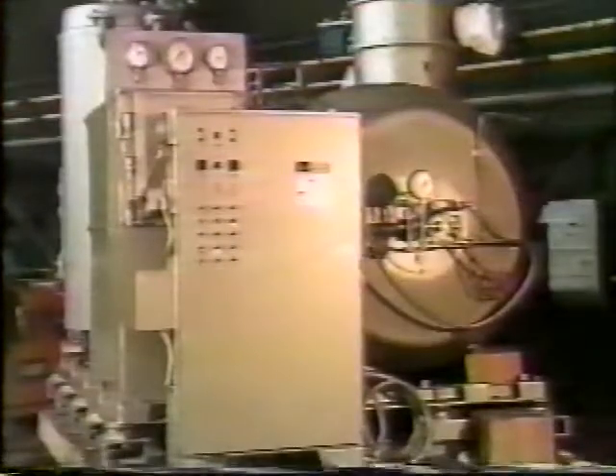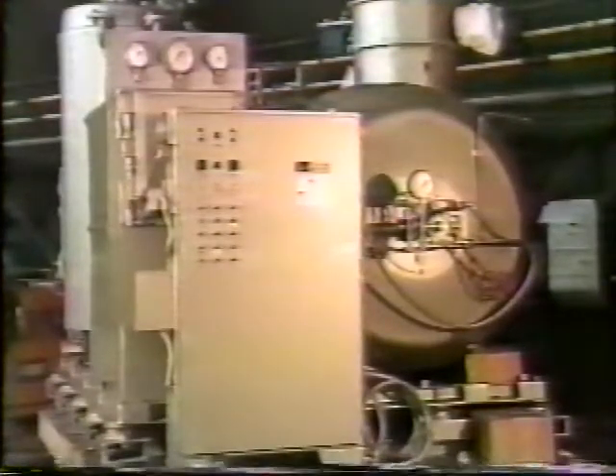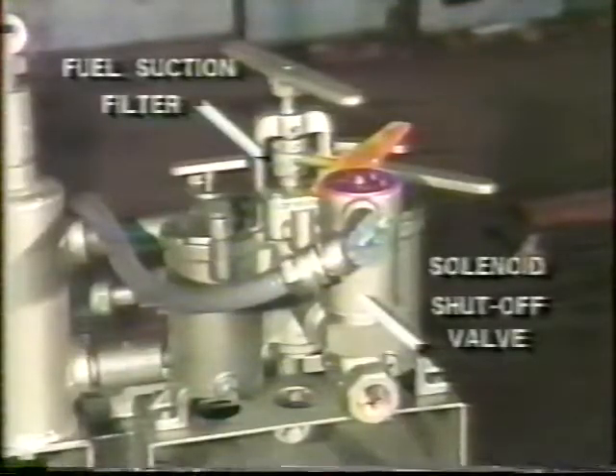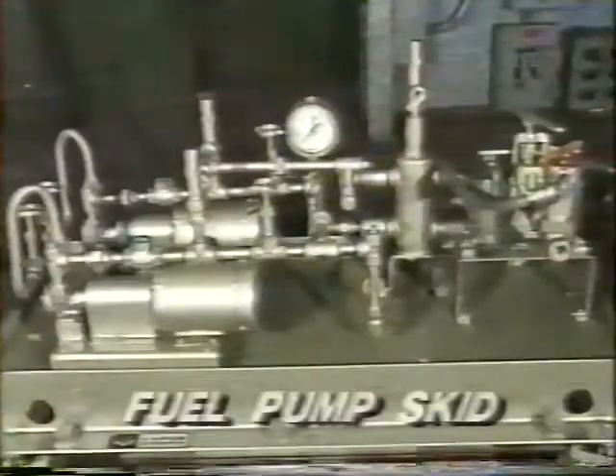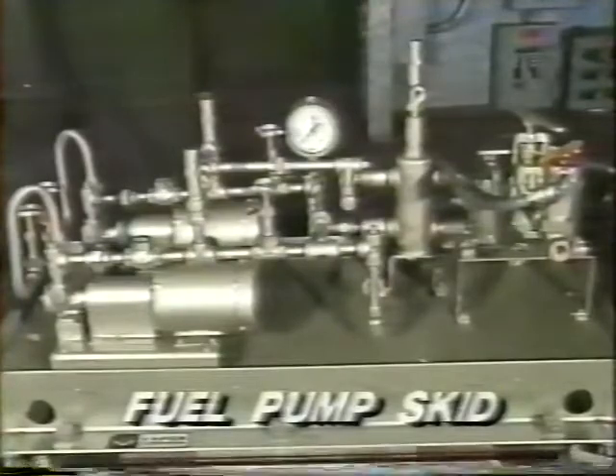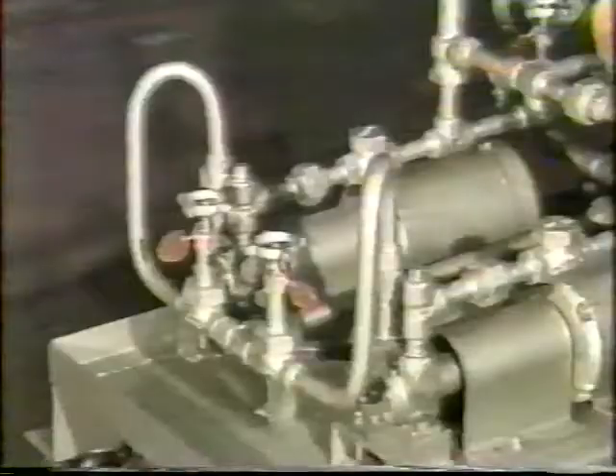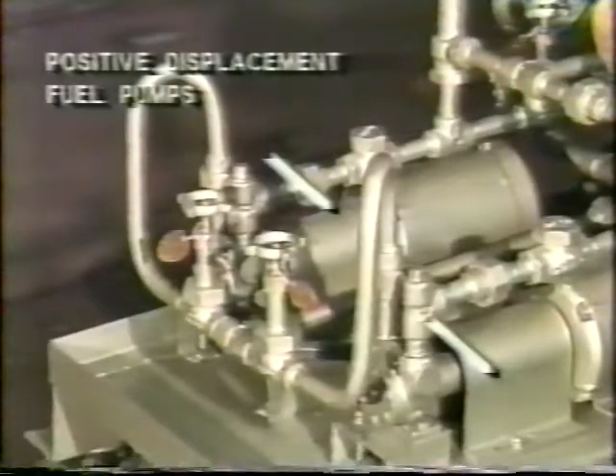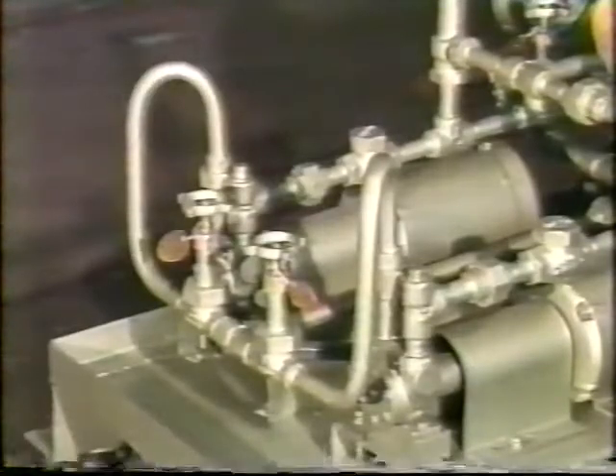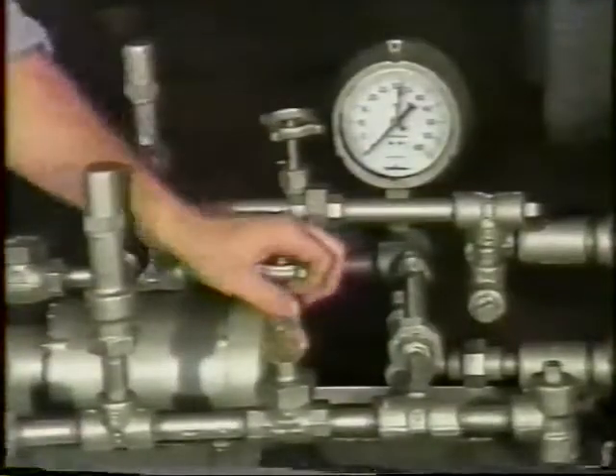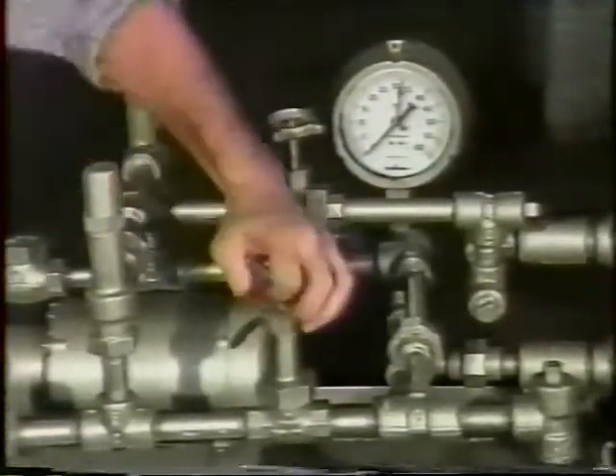Fuel to the boiler burner is supplied from a storage tank through a solenoid shutoff valve and fuel suction filter to a fuel oil reservoir on a fuel pump skid. The positive displacement fuel oil pump draws fuel from the reservoir through a manual shutoff valve and supplies it to the boiler.